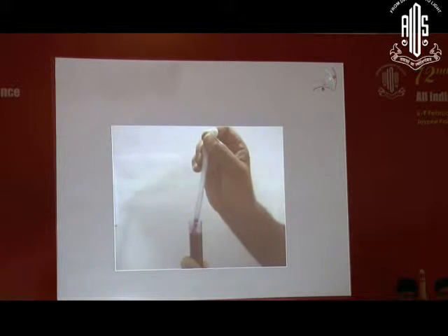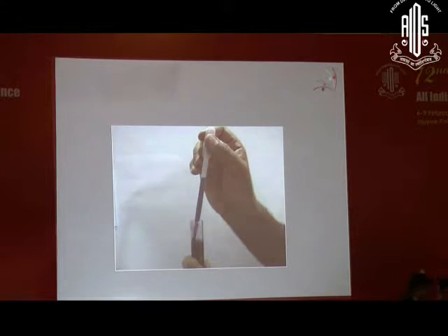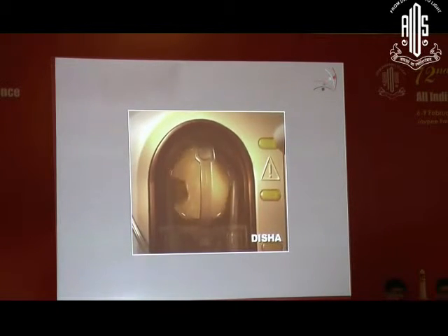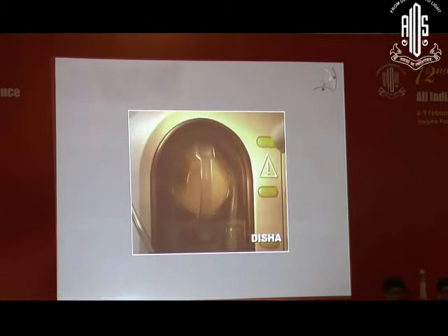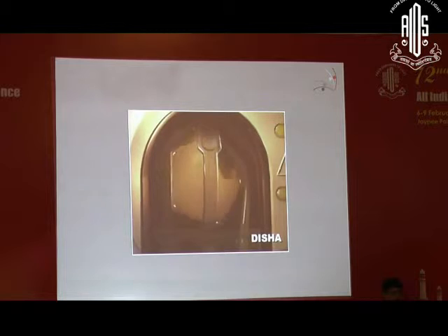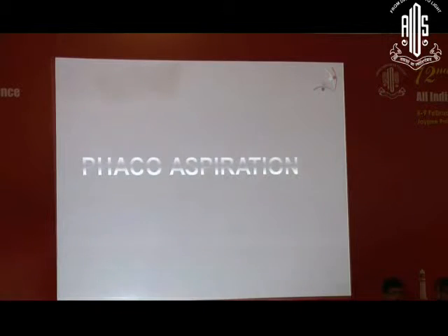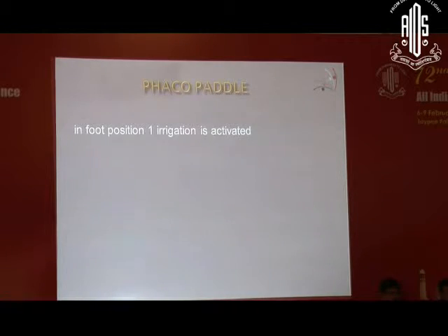Now most of these machines are peristaltic machines, and there is nothing great about it. It's like the way we used to fill up our old ink pens. So the tubings are pinched by the roller balls every now and then, and that is what causes the aspiration. So there is a motor which rotates these roller balls around the tubings. Faster the machine rotates, more is the aspiration flow. Slower the machine rotates, slower is the aspiration flow. As simple as that. So as I was telling you, it is phaco aspiration. What we can't aspirate, we emulsify and aspirate. So it is nothing out of the world, or those big machines shouldn't be scaring us.